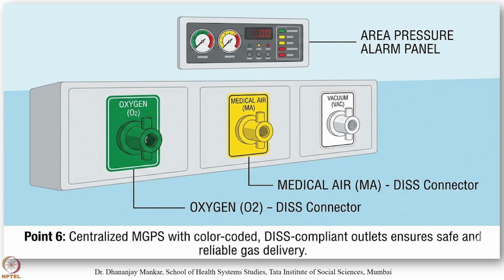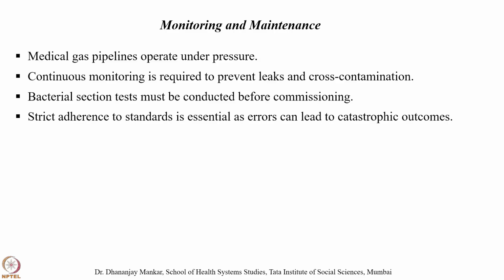The centralized MGPS with color-coded and DISS-compliant outlets ensures safe and reliable gas delivery, which is seen with oxygen in green, medical air, that is MA, shown in yellow, and vacuum, that is VAC, shown in white. The area pressure alarm panel is also displayed over here, and you may find the connectors as well as the parts of the system color coded, which gives more reliable gas delivery and ensures safety.